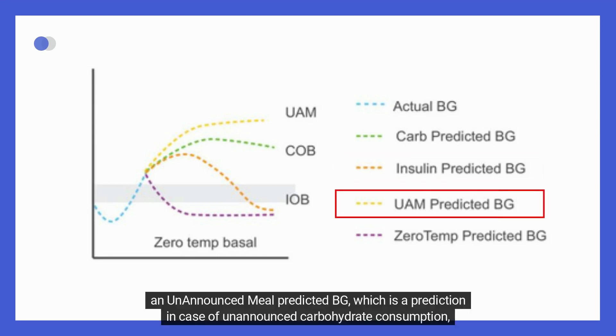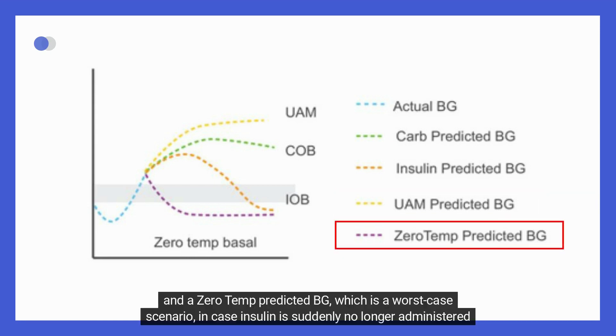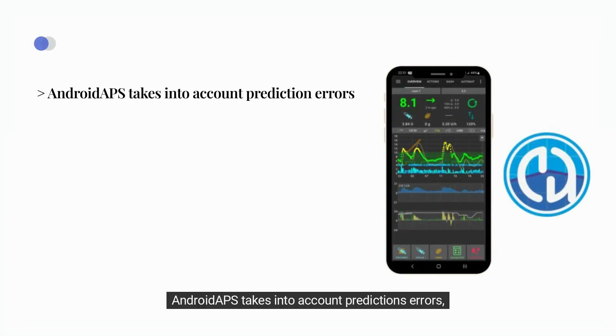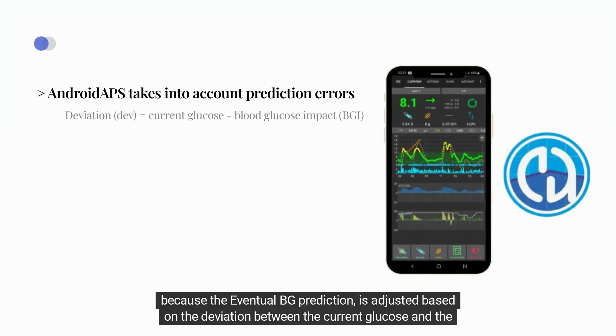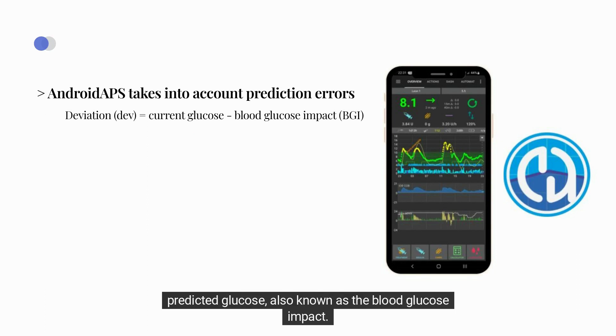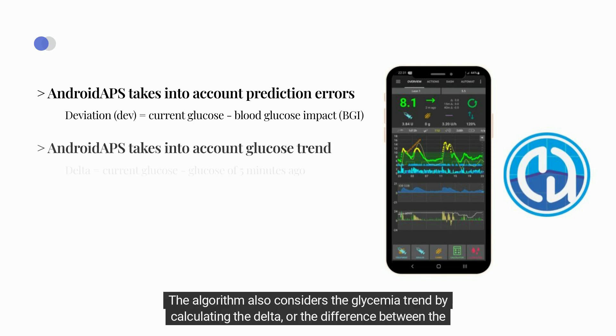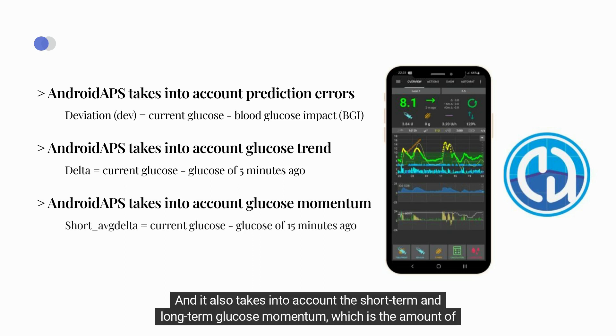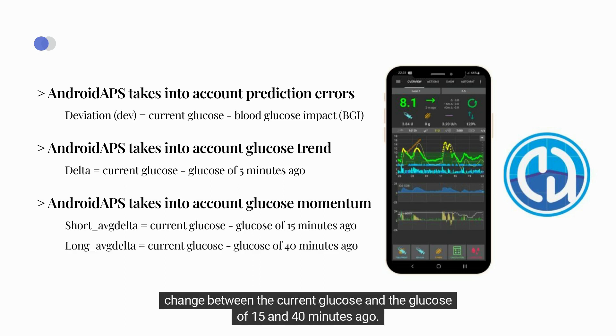Android APS also calculates an unannounced meal predicted BG, which is a prediction in case of unannounced carbohydrate consumption, and a zero-temp predicted BG, which is a worst-case scenario in case insulin is suddenly no longer administered or carbohydrates are no longer absorbed. The algorithm accounts for prediction errors, adjusting the eventual BG prediction based on the deviation between the current and predicted glucose, known as the blood glucose impact. It also considers the glycemia trend by calculating the delta, or difference between current and past glycemia, as well as short-term and long-term glucose momentum — the amount of change between the current glucose and the glucose of 15 and 40 minutes ago.